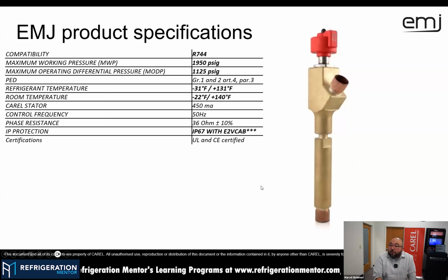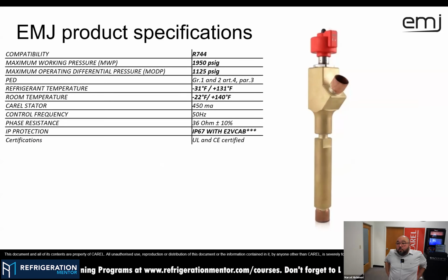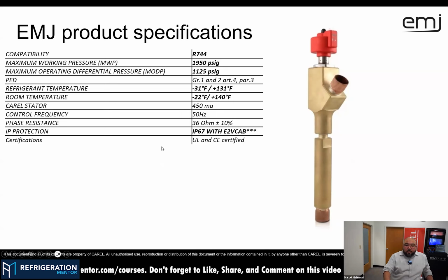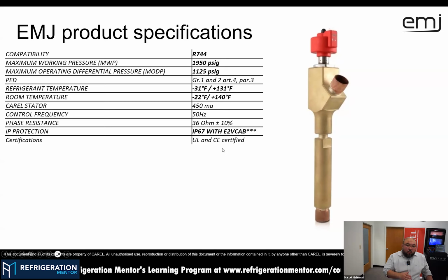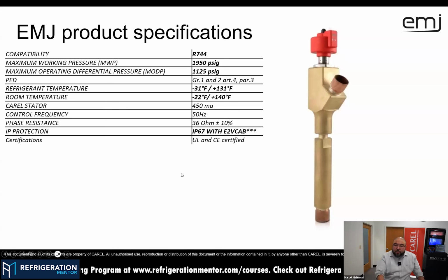So here we have this moving needle making the adjustment of the flows. And this is the spec of our ejector. It's a device rated for higher pressures. You can use it in transcritical conditions with no limitation. It has the same protections as our electronic expansion valves. It's well certified, so we are really ready to start this product in the US market. We have multiple OEMs testing this in laboratories. So if you are a technician, be prepared, because this year you will most probably start seeing more and more ejectors in the field. We have a couple of installations already done. Now that the OEMs have knowledge about transcritical systems, they are trying to improve their units with ejector technology.